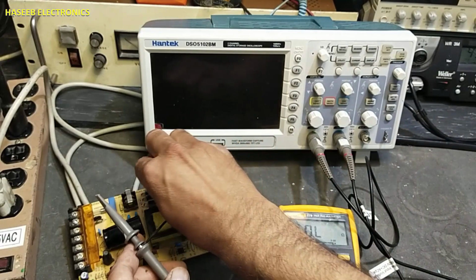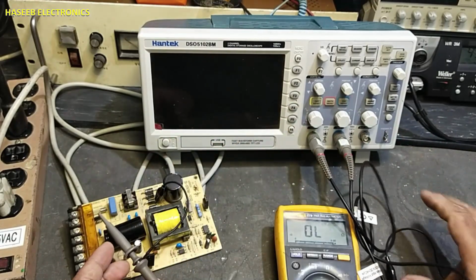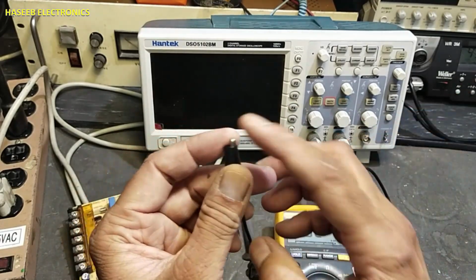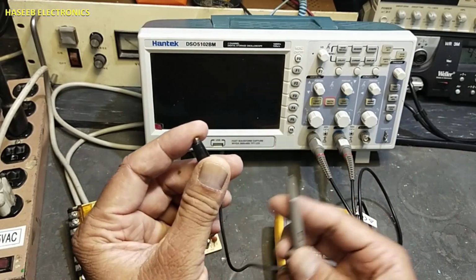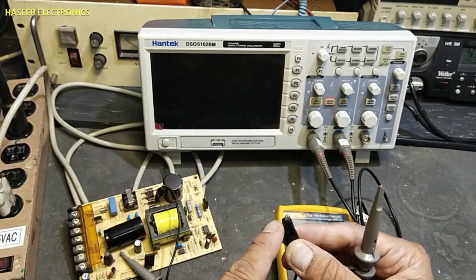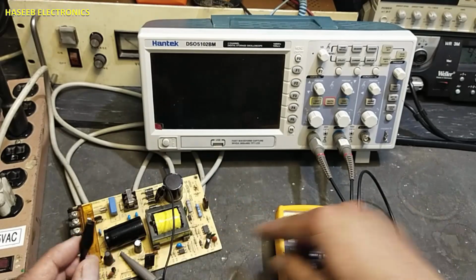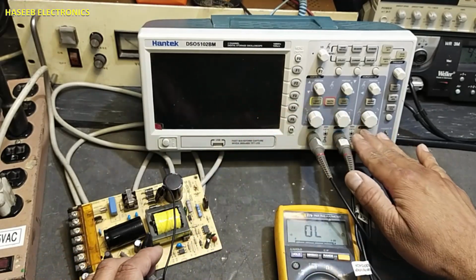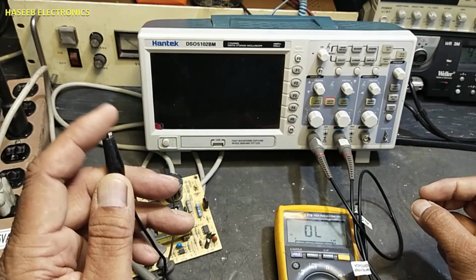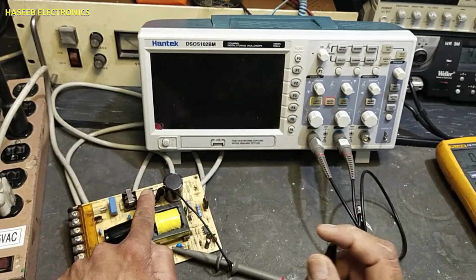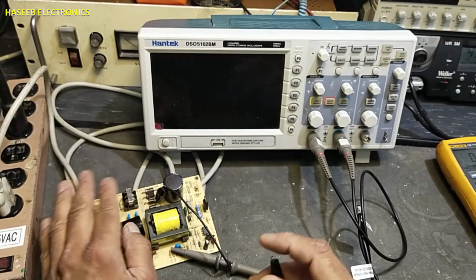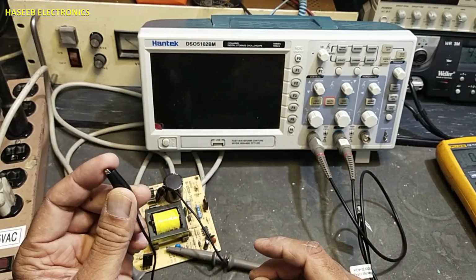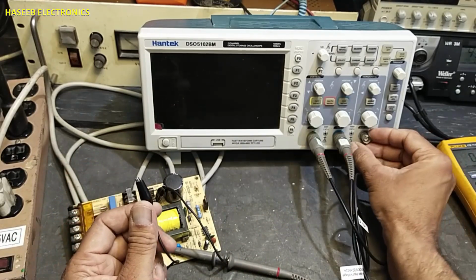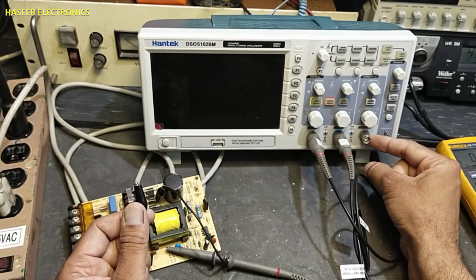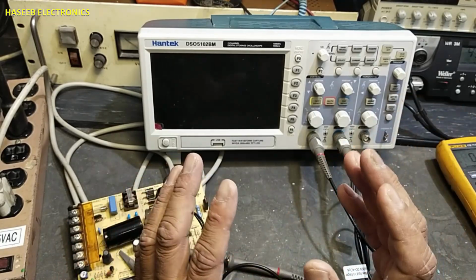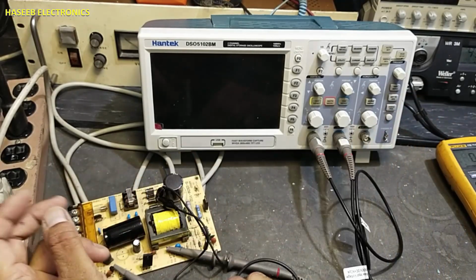If you connect this probe here and then also touch here, you will be exposed directly to this line voltage. Why? Because these low side probes are connected to the same point. It becomes dangerous when connected to any test point which is unisolated, and if we touch this low side, or while adjusting we touch this connector's outer shell, we are exposed to electrical voltage. We must be careful about these points.